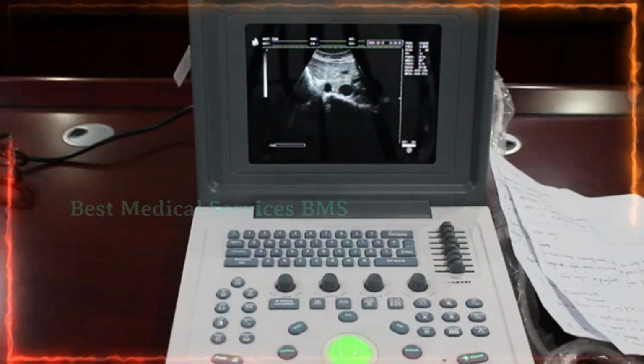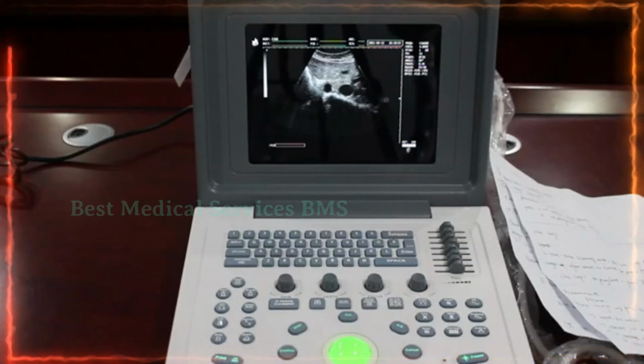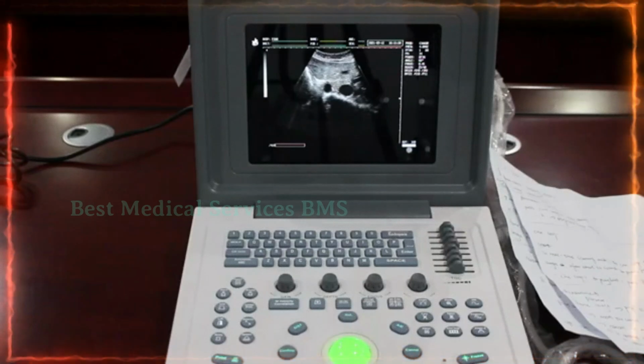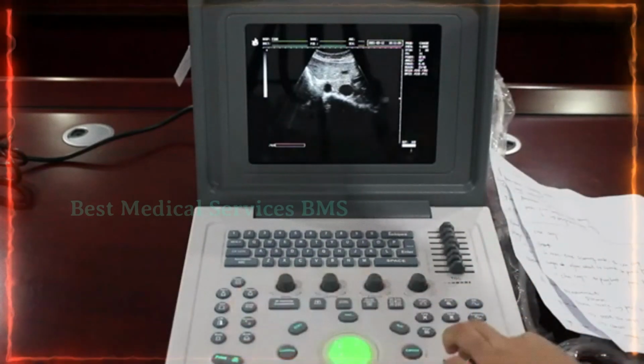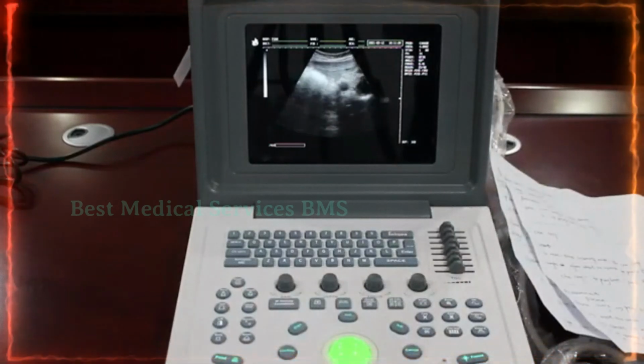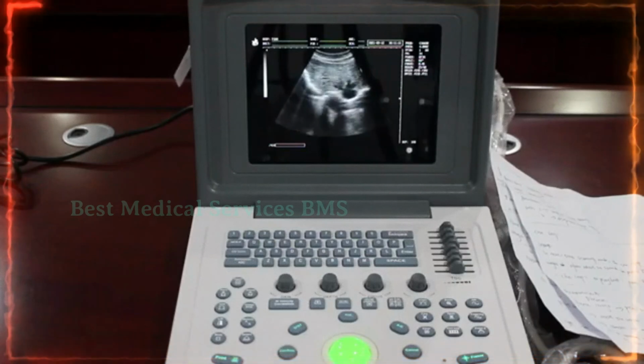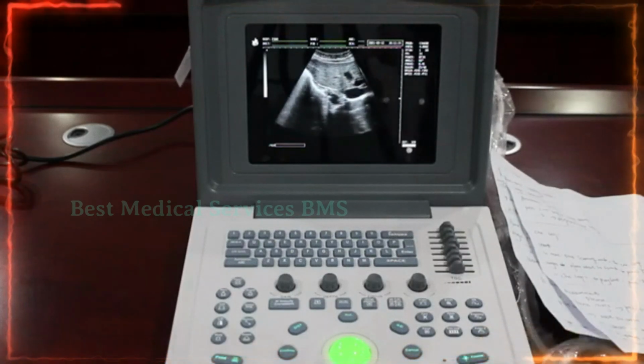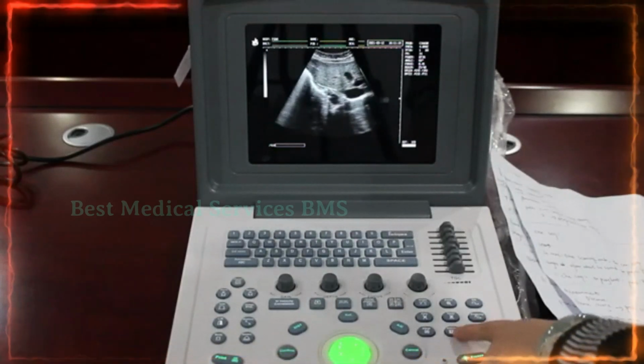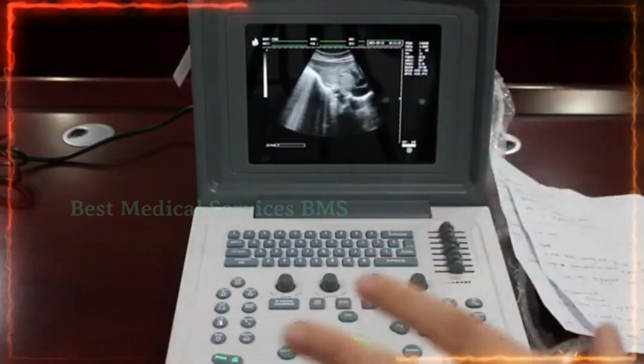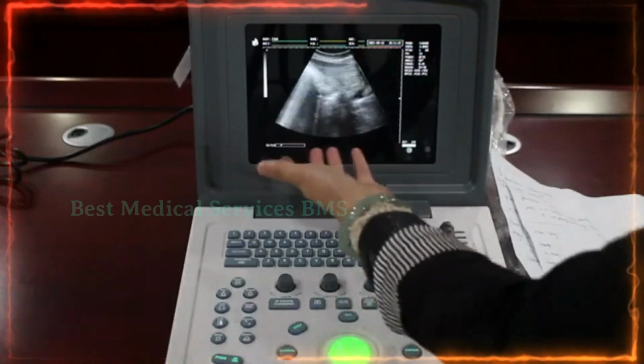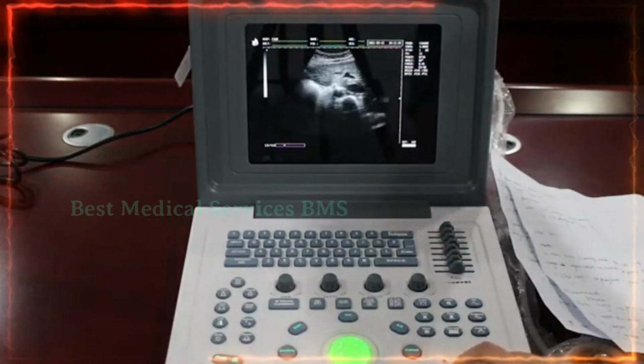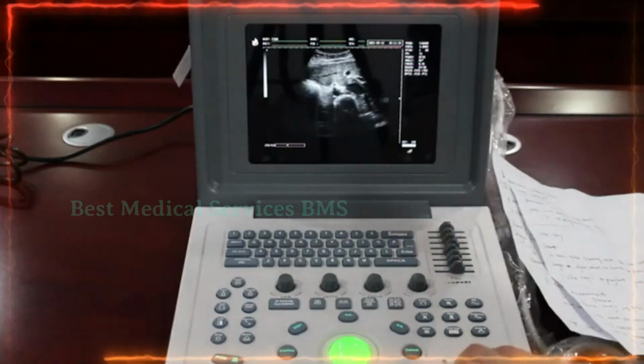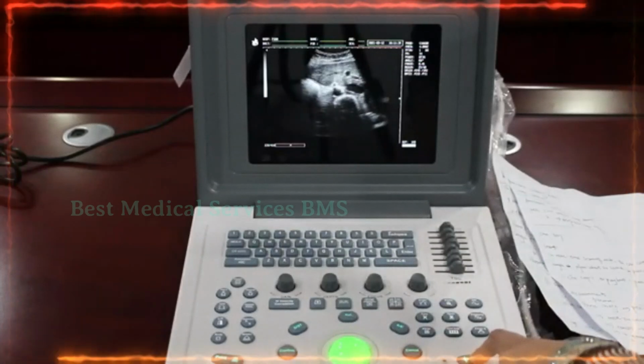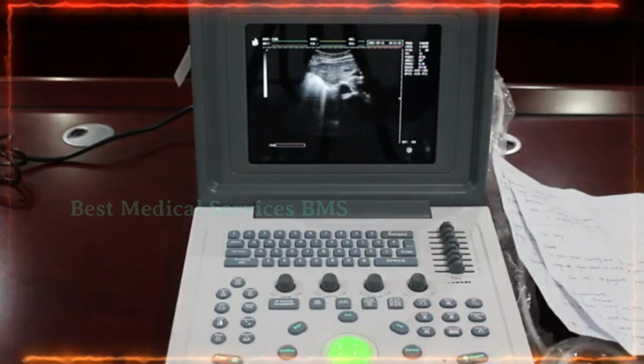Sometimes we need a cine loop to play back the images. For a cine loop, it needs around 30 seconds to collect the images. So we have to scan for around 30 seconds, and then freeze it. Press the cine loop button. This is the cine loop button, and then you can see the past videos. If you want to exit, then press the freeze button, and you are back to the real-time scanning mode.